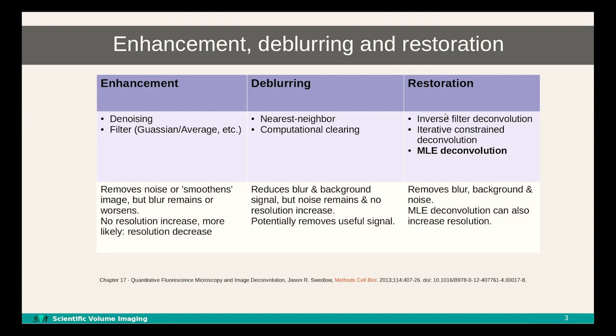Important to realize is that restoration techniques incorporate actual knowledge on the image formation process, including the microscope point spread function. They have in common that they can reduce noise, increase contrast, reduce background, and reduce blurring, all simultaneously. And in addition, the MLE restoration methods specifically are also able to increase resolution in your images.